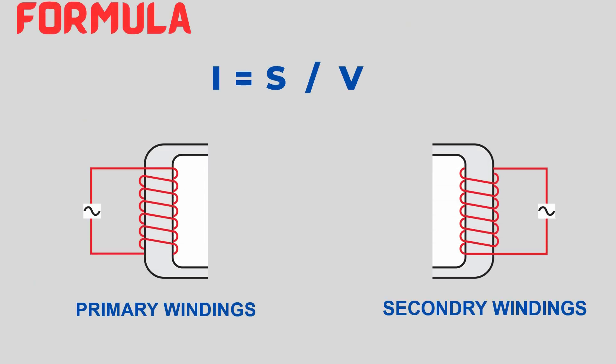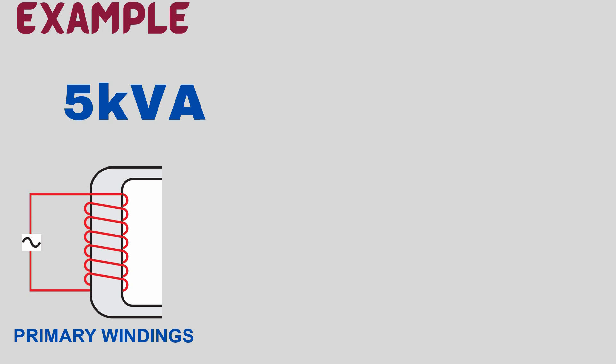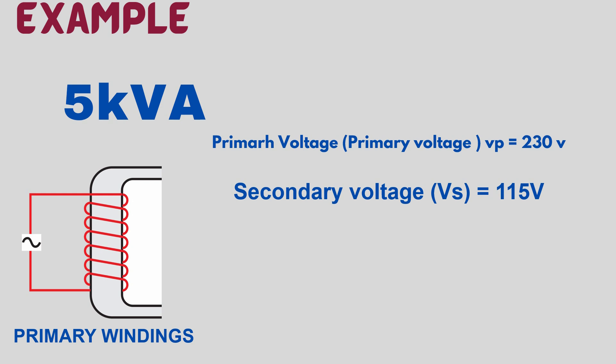For example, suppose we have a 5 kVA transformer with primary voltage 230 volts and secondary voltage 115 volts. Calculate primary current: put the values in the formula, 5000 divided by 230, so the answer becomes 21.74 amperes. So the primary full load current is 21.74 amperes.